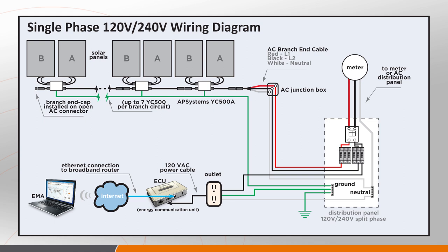This is a simplified typical residential single-phase system diagram for the YC500A microinverter. The YC500 is assigned to two PV modules, typically described as side A and side B. When hooking up the AC cabling, there are three conductors: the red L1, the black L2, and the neutral, which is used in the PLC communication with the ECU. A quick word on ECU placement: the ECU is plugged into a standard 120-volt outlet, and you want to get it installed as close electrically as possible to the array to eliminate as many communication problems as possible.